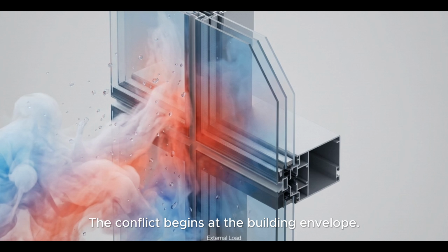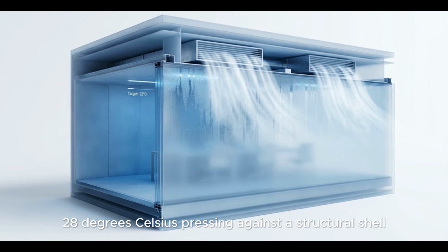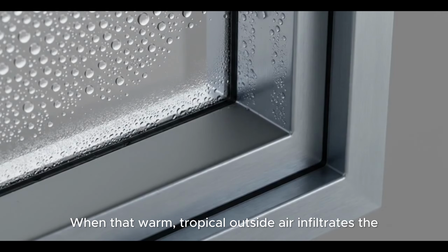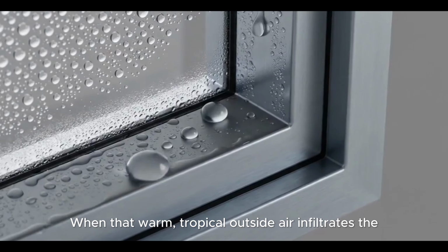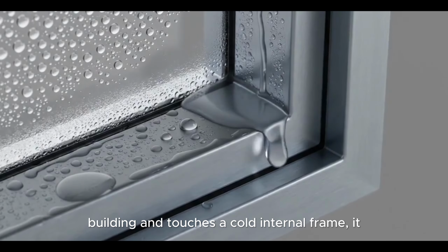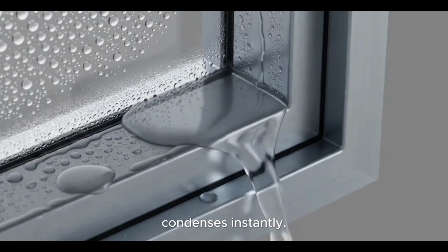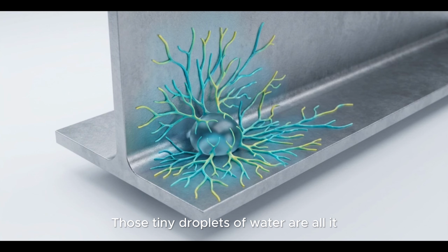The conflict begins at the building envelope. You have heavy, moisture-laden outdoor air at 28 degrees Celsius pressing against a structural shell that's aggressively chilled and dried by internal air conditioning. When that warm, tropical outside air infiltrates the building and touches a cold internal frame, it condenses instantly. Those tiny droplets of water are all it takes to trigger a biological reaction. They serve as the ignition source for rapid mold proliferation.